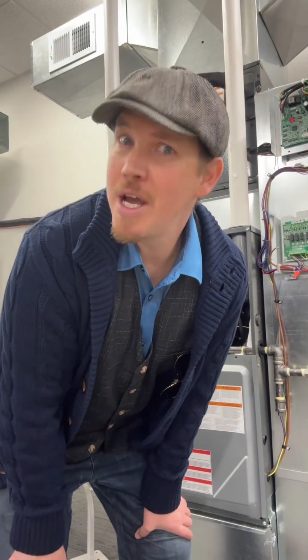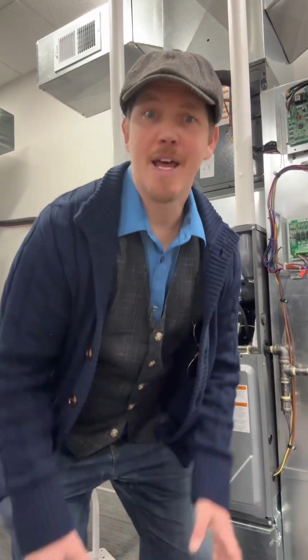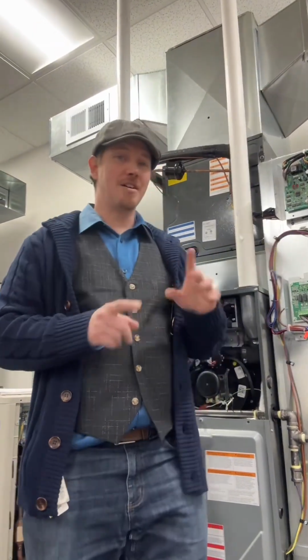Do you even check static, bro? Do you know where to check static? Do you know why to check static? Static pressure is probably one of the biggest things on any piece of equipment that leads to all kinds of issues. First of all, if your static pressure ain't right, your airflow's not right. Second of all, if your static pressure is too high, then your system's noisy, you've got all kinds of issues going on. You're gonna reduce the oil return to your compressor.